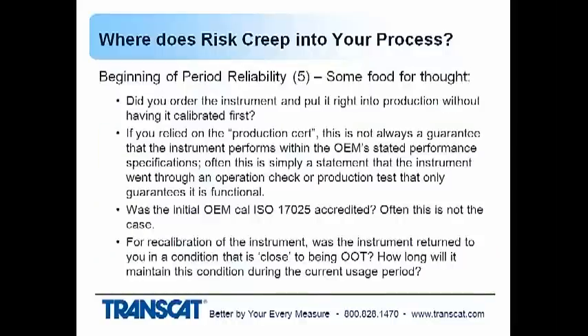Beginning of period reliability. Here's some things to think about. When you purchased the instrument initially, did you put it right into production without having it calibrated first? Did you rely on a production cert, which is not always a guarantee that it meets all of its performance specifications? Was the initial calibration 17025 accredited, which brings a lot of detail behind that? We have some white papers on that if you don't know the details of 17025 accreditation. Many times OEMs are not accredited. And then when you recalibrate the instrument, was it returned to you in a condition that was maybe close to the tolerance limit? How long will it maintain that condition through its next cal interval? So those are some of the things that you need to think about that can cause nonconformance reviews to occur, which cost you money.